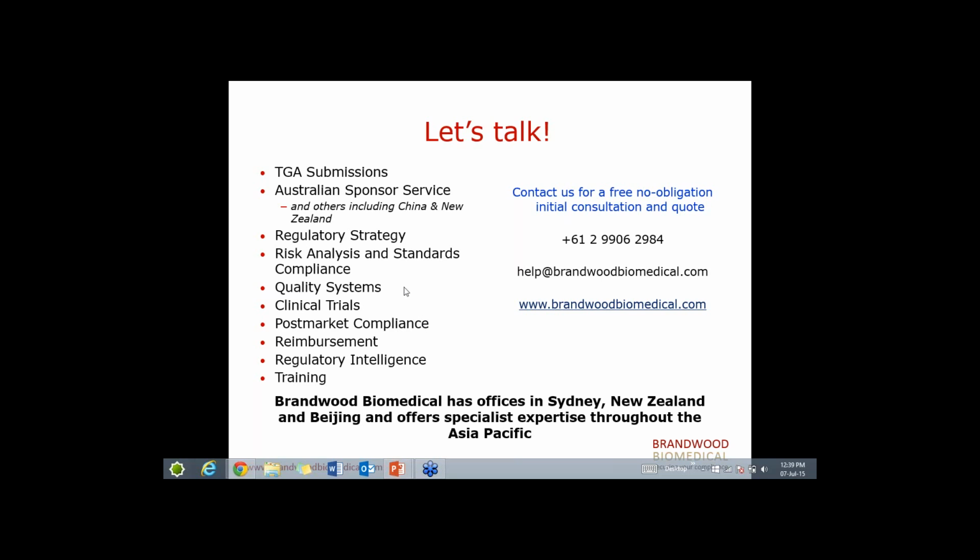Okay, the next question I've got here: how long does it take to get TGA approval if you have a CE certificate? With the timelines there's no distinct answer, but it is a much quicker process than going through TGA conformity assessment, which involves a lot of time and cost. As I mentioned before, TGA have limited resources in their devices area, so there are long timelines if you go through TGA. If you have a CE certificate, it is a much quicker process. But when we say quick, it depends on the resources of TGA.